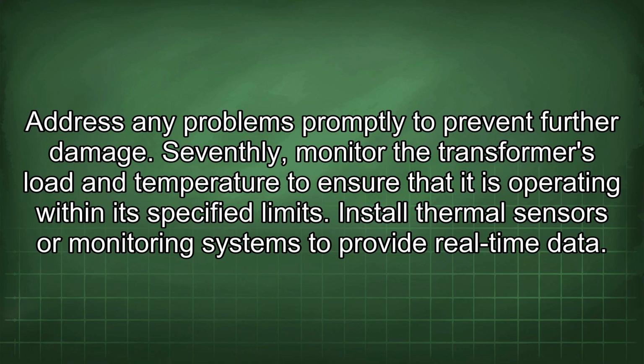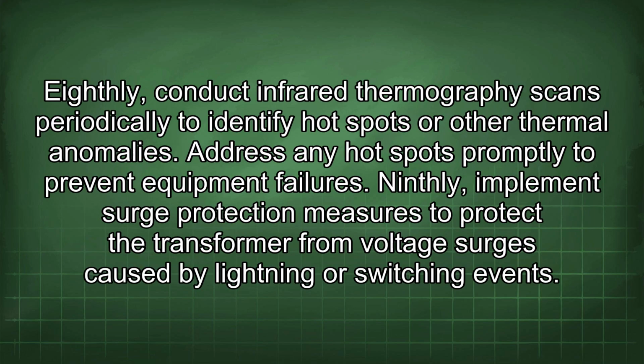Seventhly, monitor the transformer's load and temperature to ensure that it is operating within its specified limits. Install thermal sensors or monitoring systems to provide real-time data. Eighthly, conduct infrared thermography scans periodically to identify hot spots or other thermal anomalies. Address any hot spots promptly to prevent equipment failures.